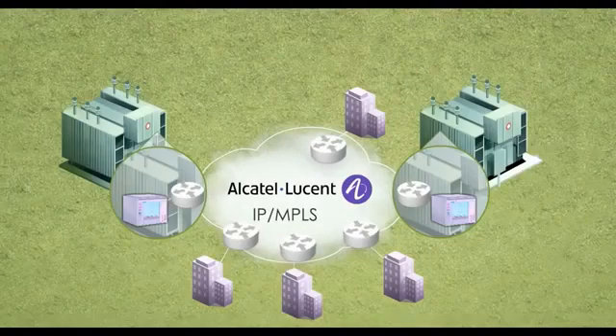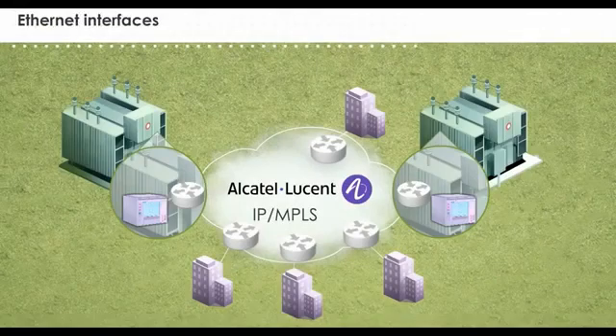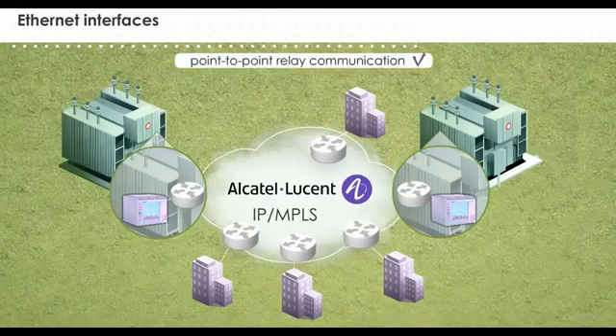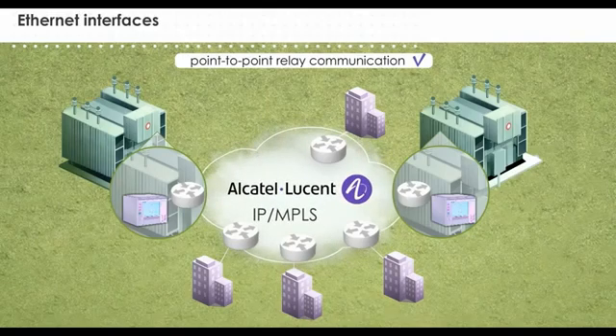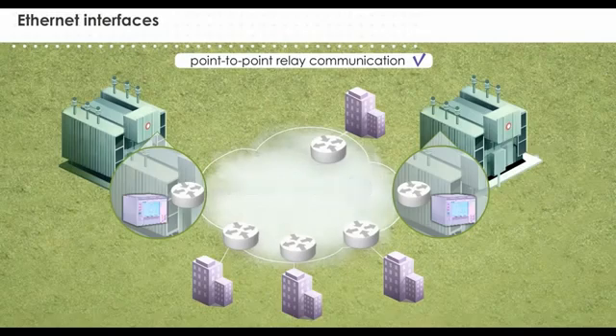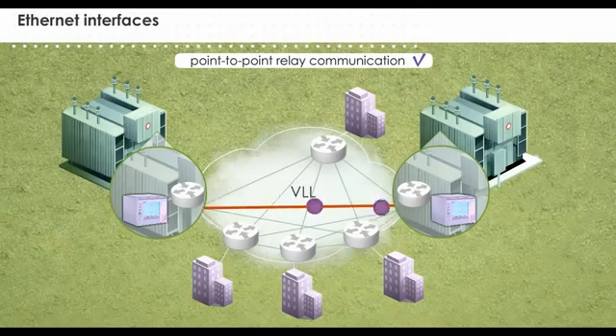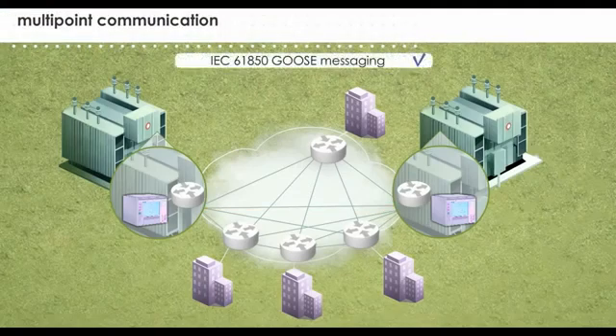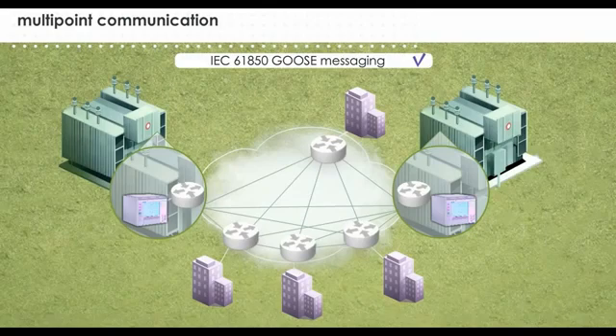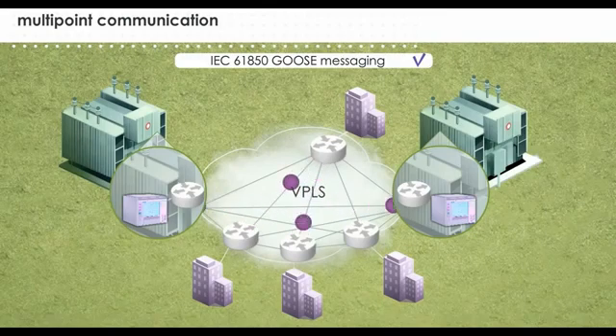New generation relays utilize Ethernet interfaces. Point-to-point relay communication can be supported with an Alcatel-Lucent IP MPLS network using Ethernet Virtual Leased Line (VLL) service. Multipoint communications such as IEC 61850 GOOSE messaging can be supported using Virtual Private LAN Service (VPLS).